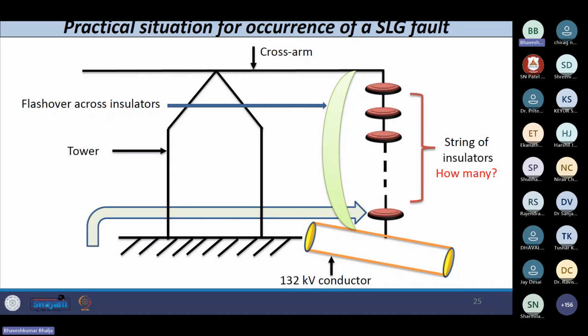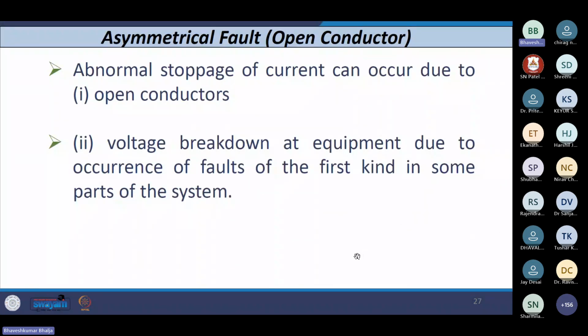Then the voltage becomes, let's say, 332 kV, and the string is capable of withstanding 132 kV by root 3 multiplied by root 2. So only that much value it can withstand. If 332 kV comes across this, there is a flashover across these insulators, and hence from conductor to cross arm, which is at ground level, a line to ground fault occurs. So this is the simple way how a line to ground fault occurs.